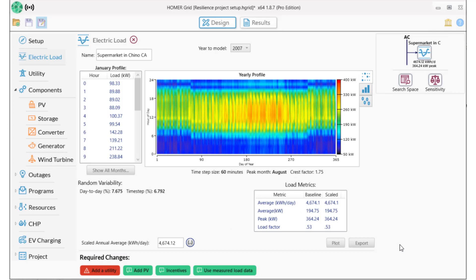I want to divide the load into critical and non-critical amounts in order to only serve the critical load during an outage. I'm going to use Homer's ability to scale a load profile to change this load to about half this amount — 2,350 kilowatt-hours per day.